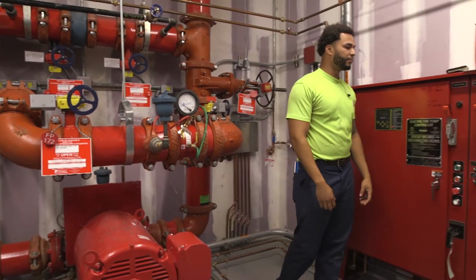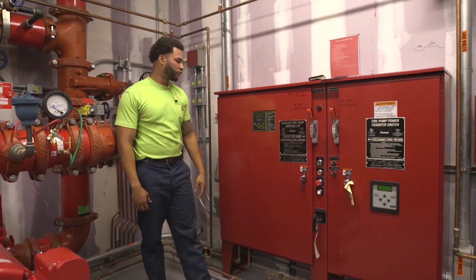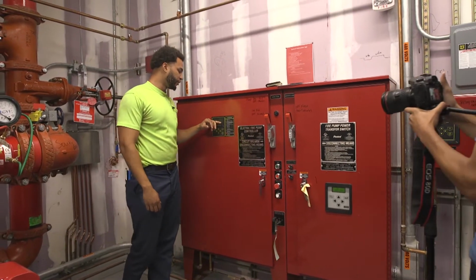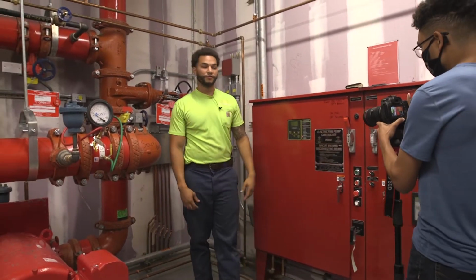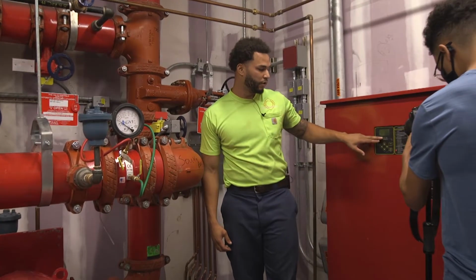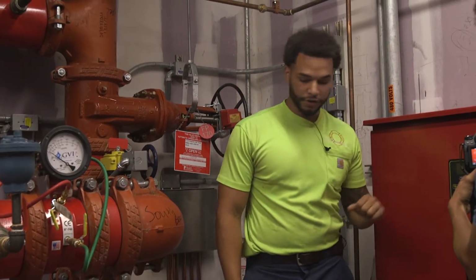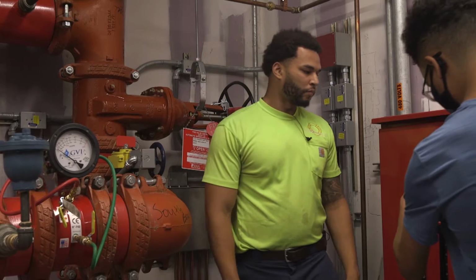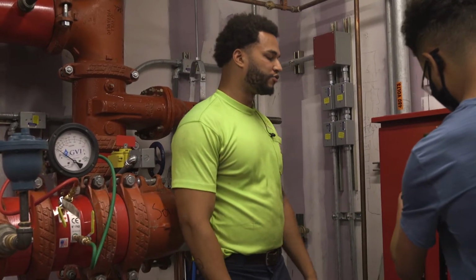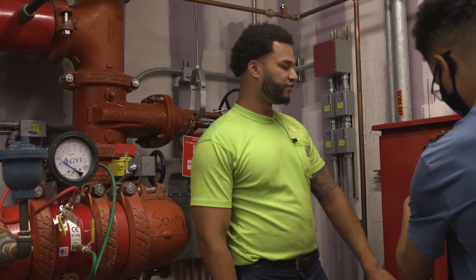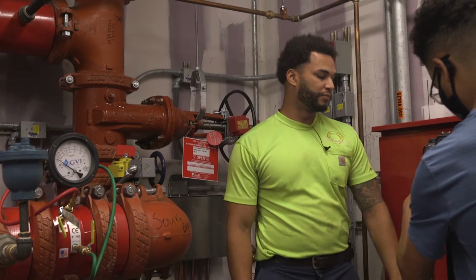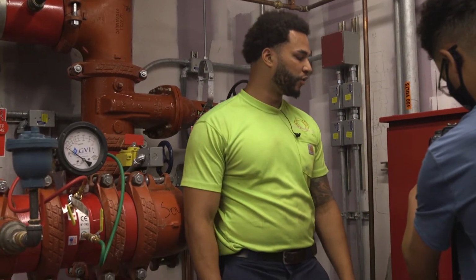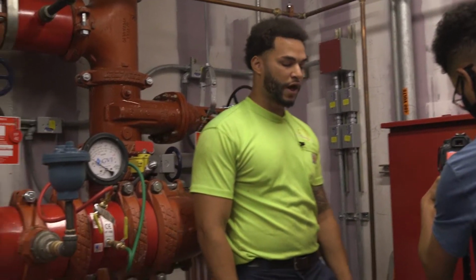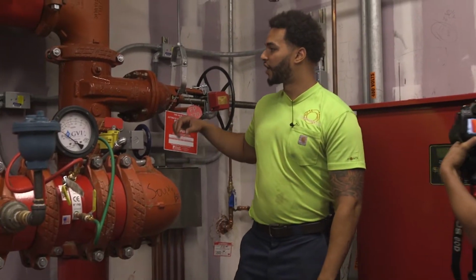A couple things to keep in mind before we operate this equipment. We do have 400 plus volts actually coming into this fire pump control panel, which can be seen over here across the LED screen. So this would be your electrical hazard. For no reason would you want to open up this control panel and go into it because of that electrical hazard.